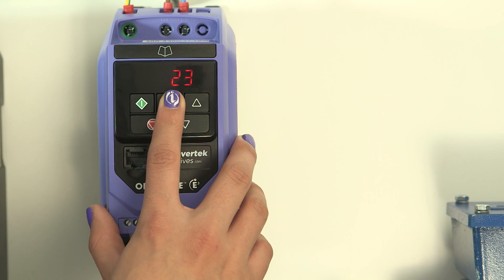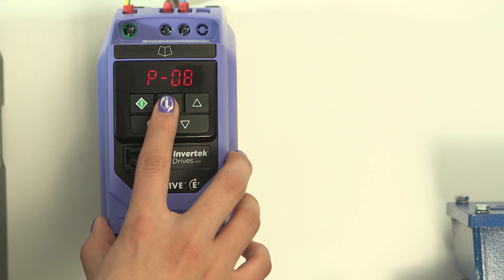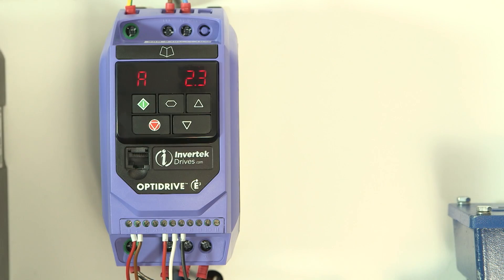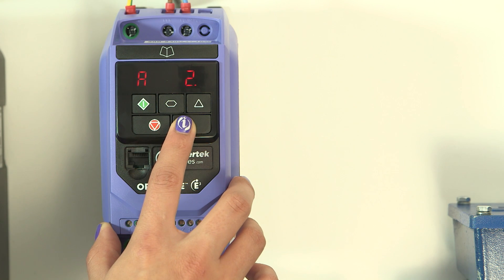Press navigate again and then scroll to the next parameter, parameter 8. This is the motor current rating which is important for protection. The rating plate on this motor says 1.9A for delta connection which we have here. Set that using the up and down arrows.